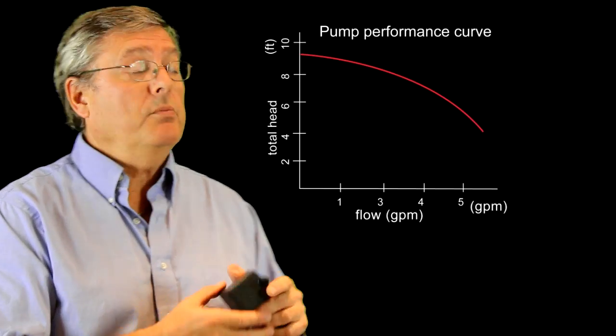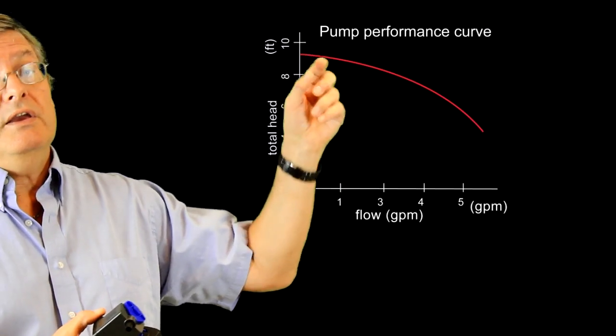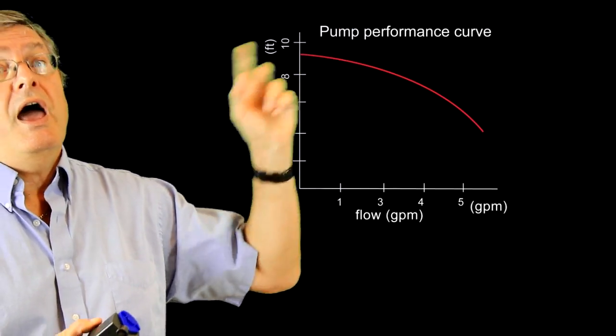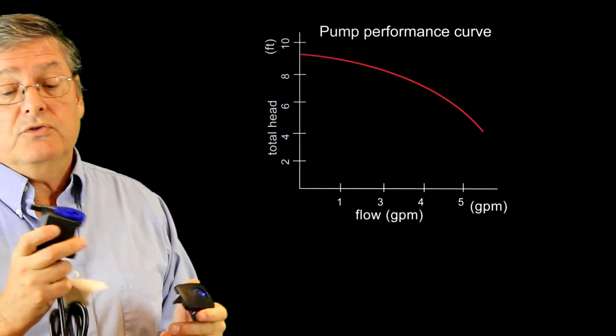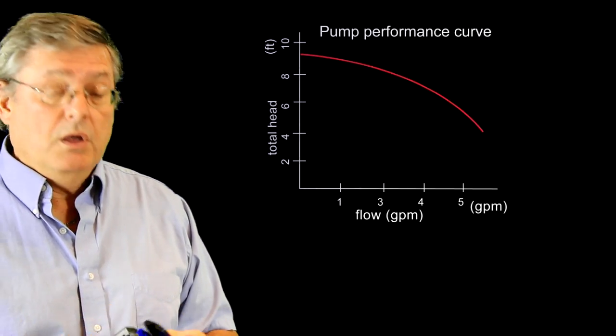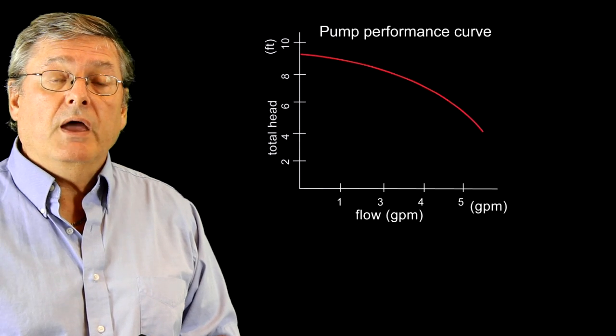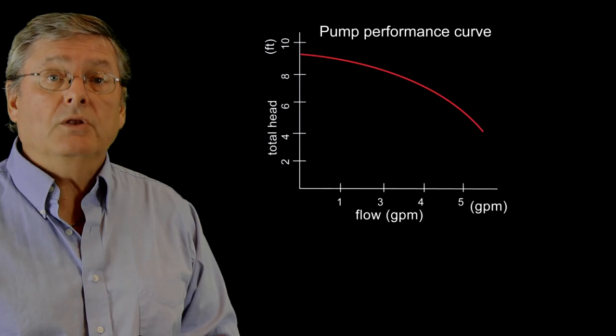So it says here, this is the information they give us, that this pump will provide 140 gallons per hour to one foot of head. Not very much, but you know, if I need lower flow, I know because of this curve that I can get higher head at lower flow, and that may be just fine for what I need. So there we are. Happy pump buying and good luck.